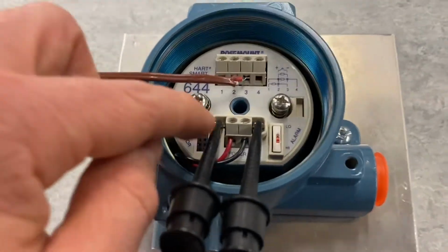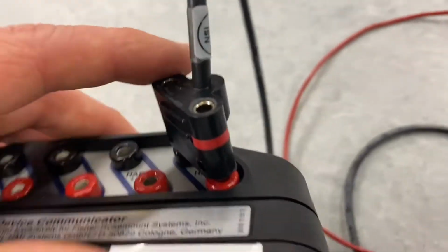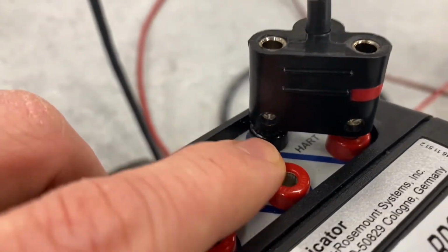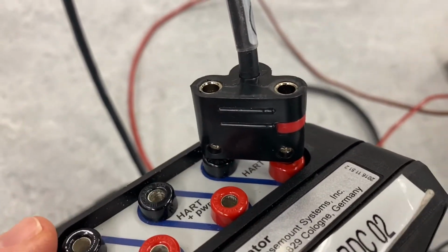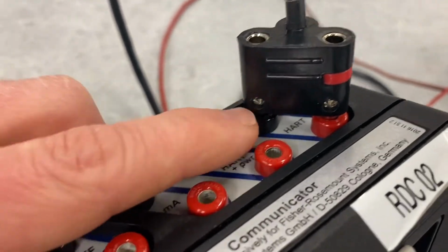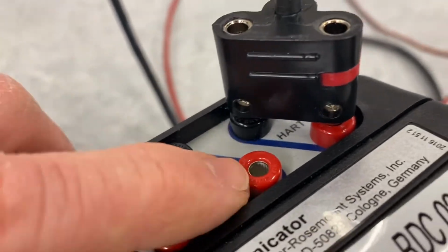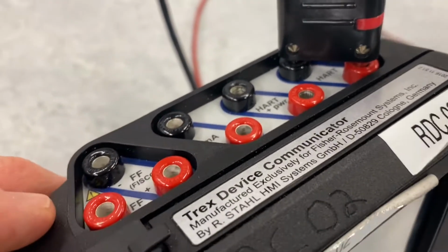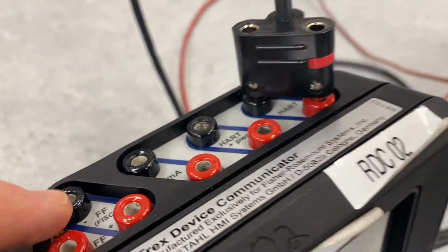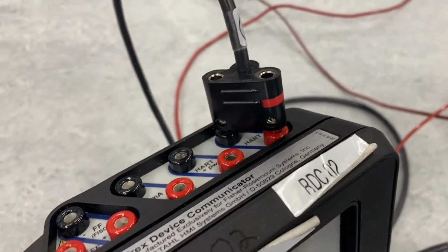It connects across these two hook leads right here, which then go into the top of the communicator over here. On this side, you can see we're in the HART side. That's the communication protocol that we use to communicate with the device. There are some other leads here with HART power. You can measure current, and there's another protocol called Foundation Fieldbus. We're going to be connected over here on this side.